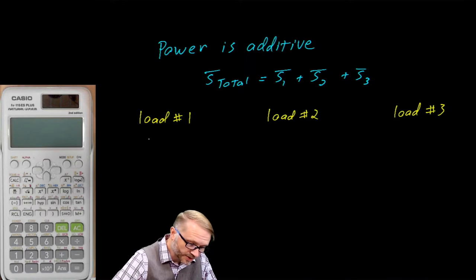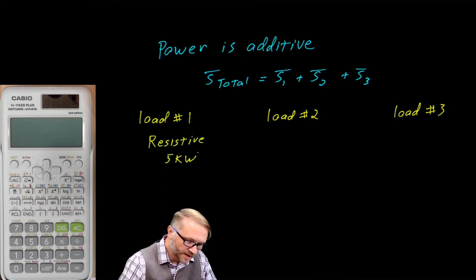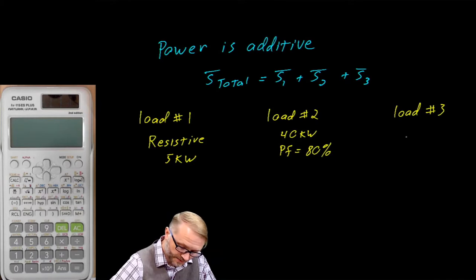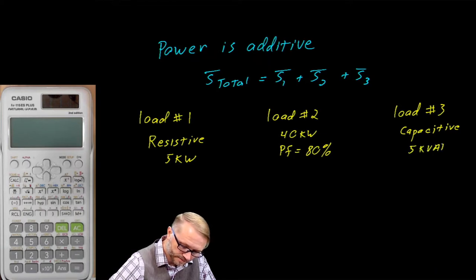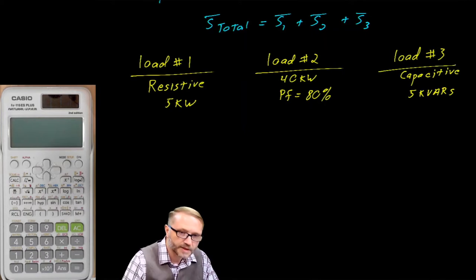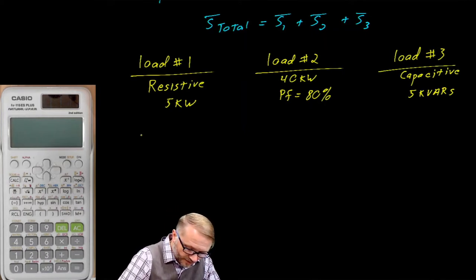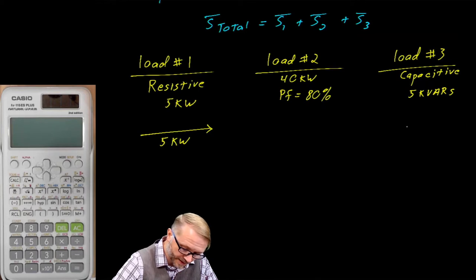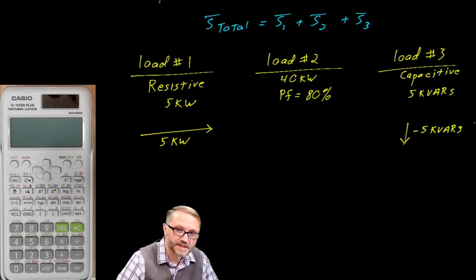We'll let the first one be pure resistive at 5 kilowatts. The second load is 40 kW with a power factor of 80%. And the third load is pure capacitive, and that will give us 5 kVars capacitive. Before you do the calculation, I would encourage you to present the power triangle for each load. The resistor is very easy — it's 5 kilowatts, all real. The capacitor is very easy because it's negative 5 kVars — it's all imaginary.